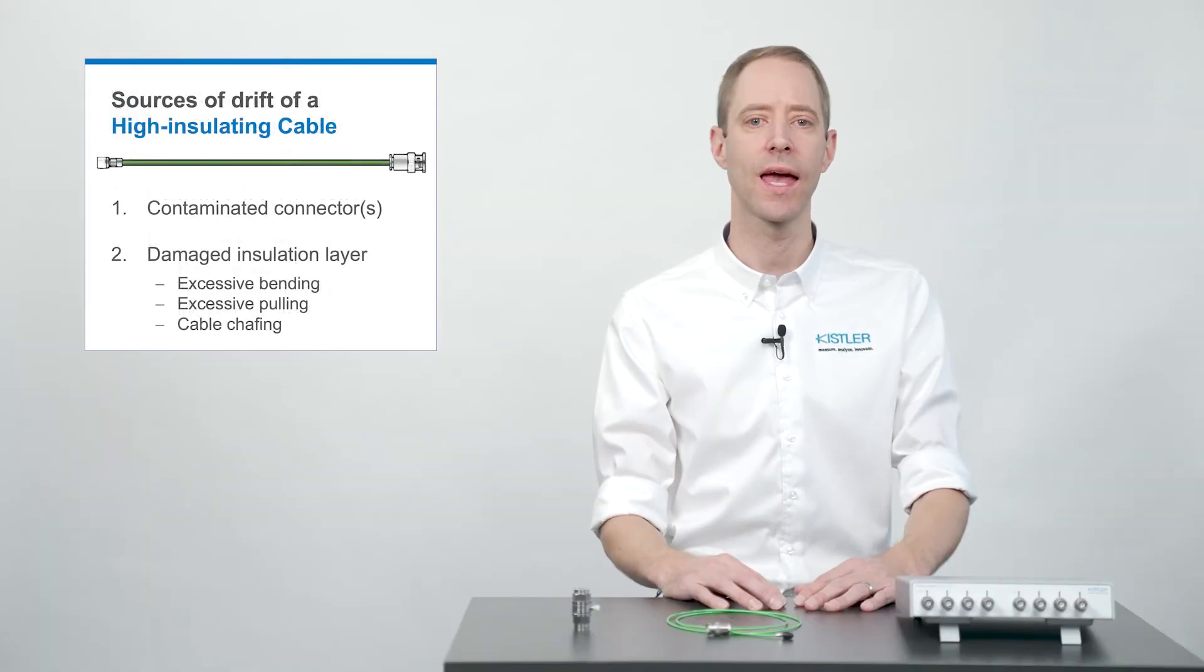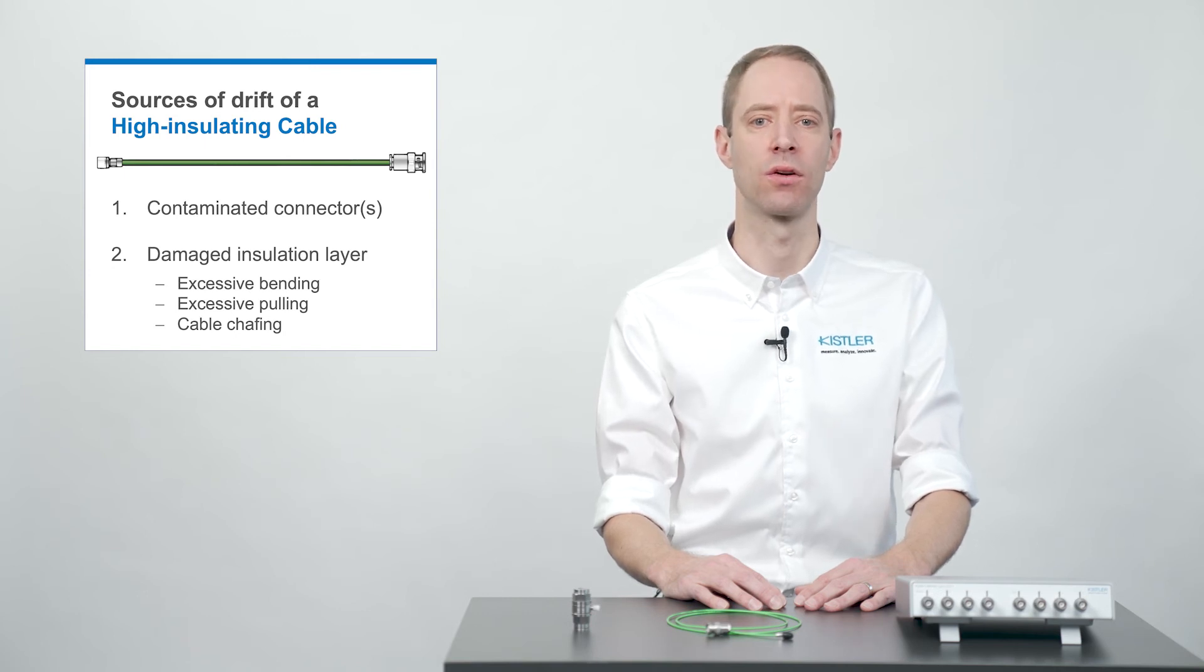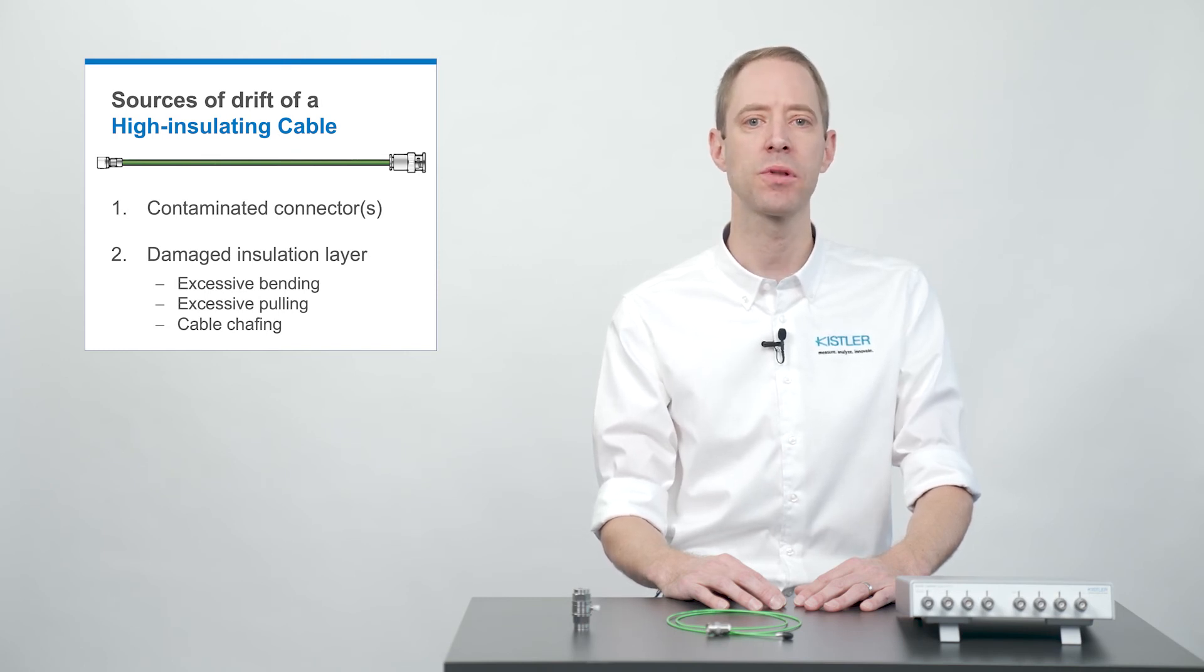For the high insulating cable, obviously, connector contamination also leads to drift. A second possible source for drift is a damaged insulation layer. Often, the damage is caused due to excessive bending of the cable or pulling on the cable too strongly, which can lead to tearing off on the connector side. In rare cases, cable chafing of a moving cable on a sharp edge can damage the insulation layer.